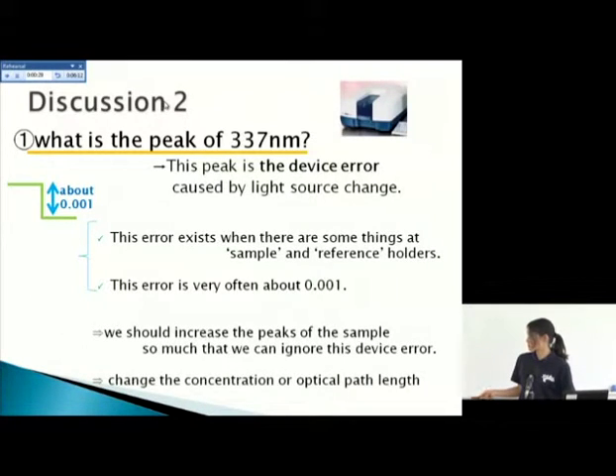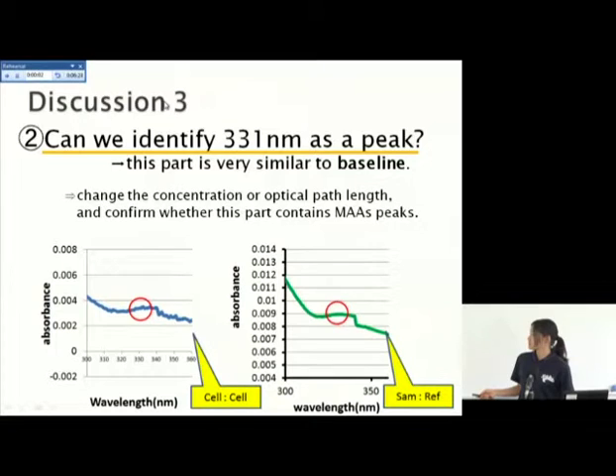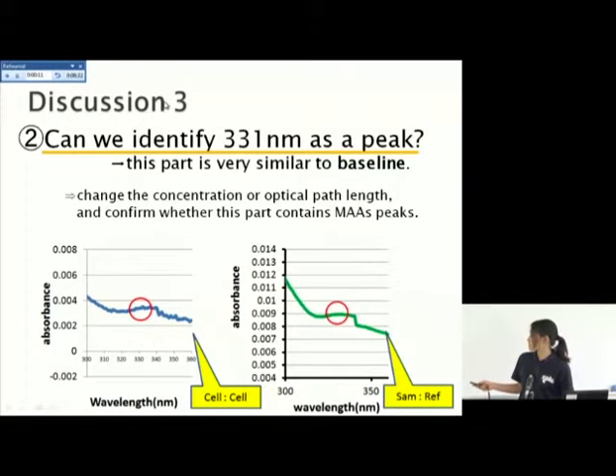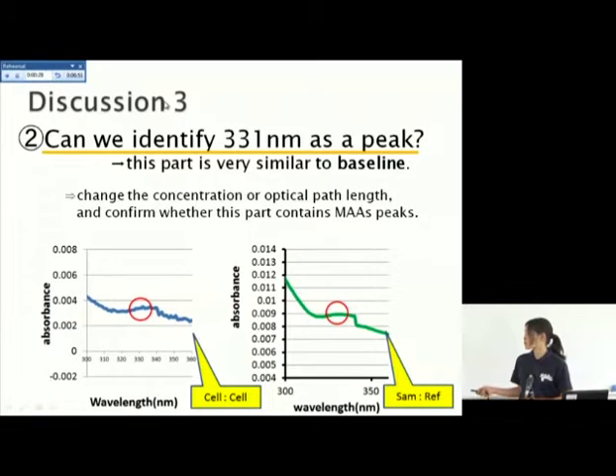Therefore, we should increase the peak of the sample so much that we can ignore this device error. We should change the concentration or optical path length in order to increase the sample peak. As for whether we can identify 331 nanometers as a peak, this part is very similar to the baseline, so we need to change the concentration or optical path length to increase the peak and confirm whether this part contains the MAAs peaks.